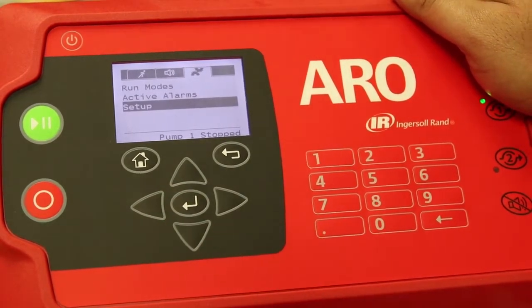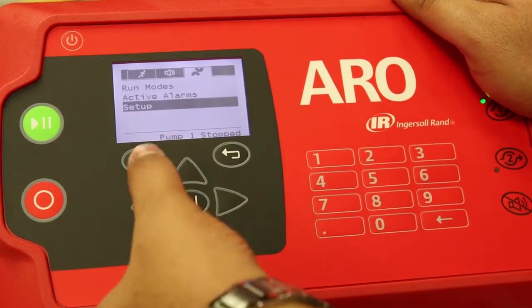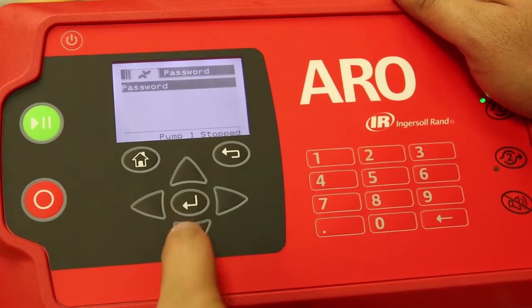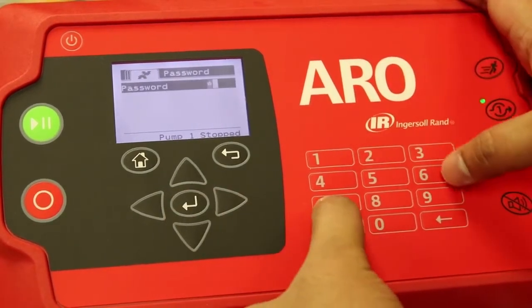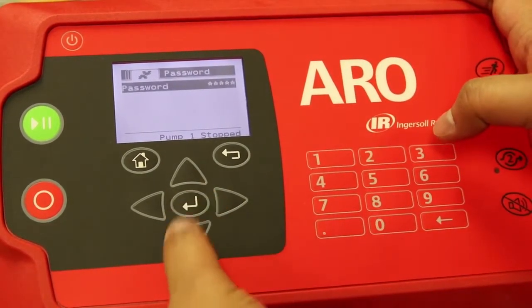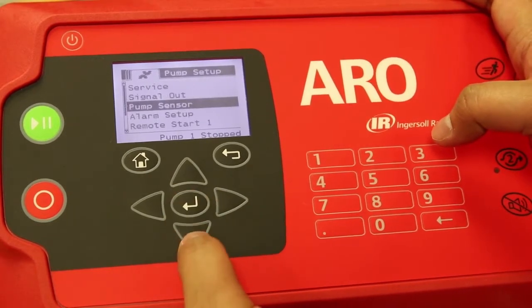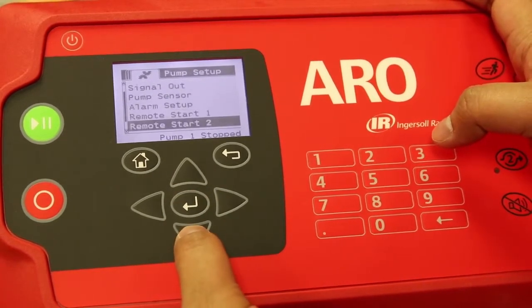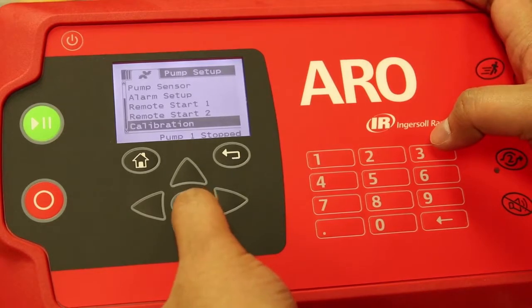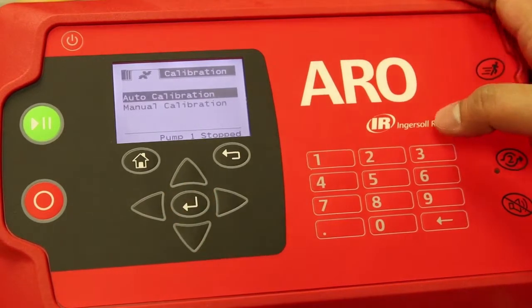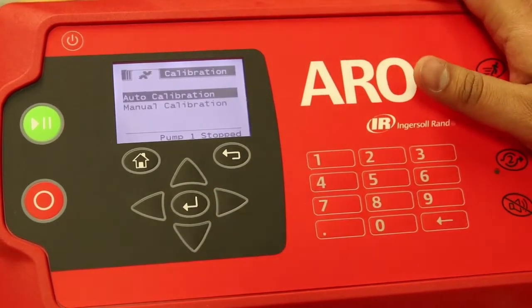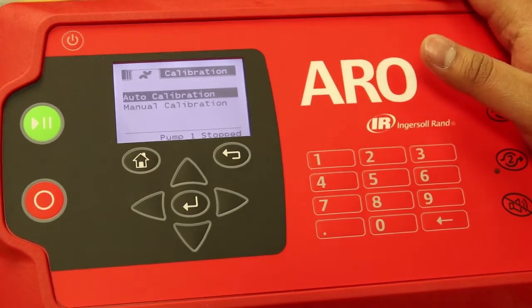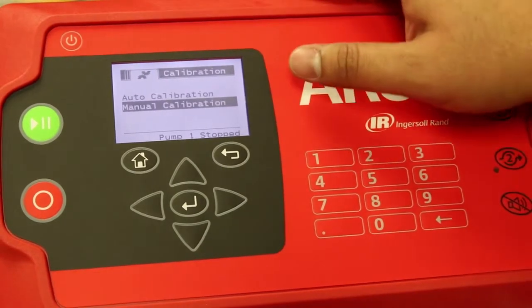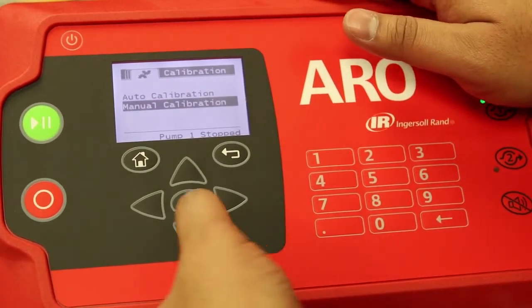Next step is to calibrate the flow meter. In order to calibrate, we'd go into the setup menu and enter pump setup and scroll all the way down to find the calibration screen. Calibration provides you with two options: auto calibration and manual calibration. To give you an example, let's try manual calibration.